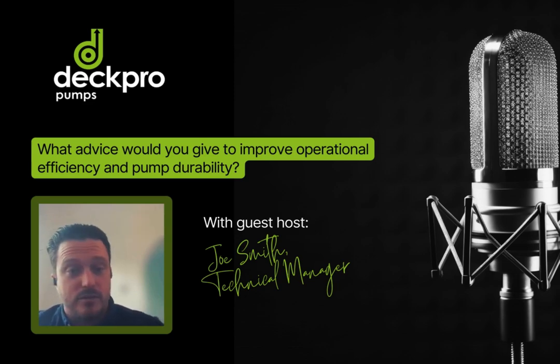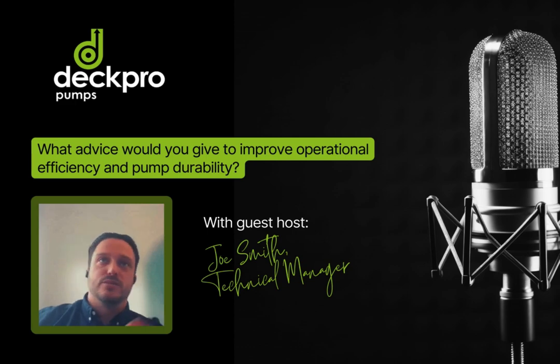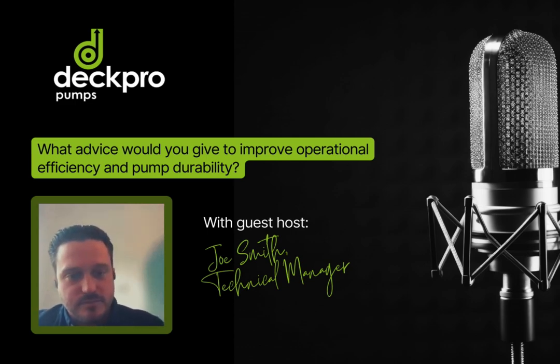And then we want it to come back on in the morning, 7 o'clock in the morning. That can all be done automatically, and it runs back on temperature demand at that point. Over a year, if you take a pump that's running 24 hours and you can just control it for 12 hours during the day, there's a lot of savings to be had. And obviously, all the time that pump's not running, it's increasing the lifespan of that pump. It's not doing its hours on the bearing. So, yeah, it's energy efficiency, also increasing lifespan of the motors.